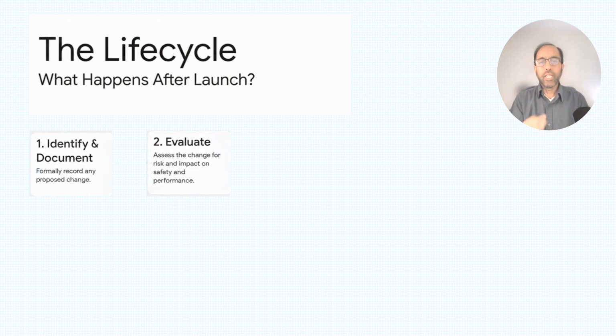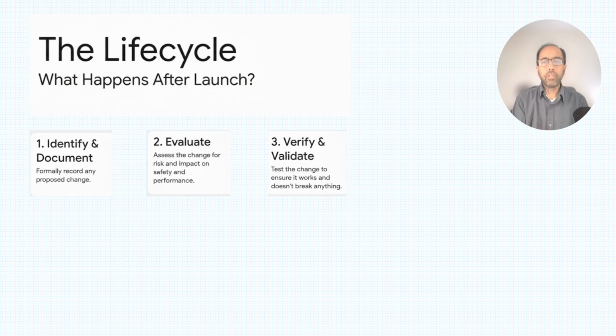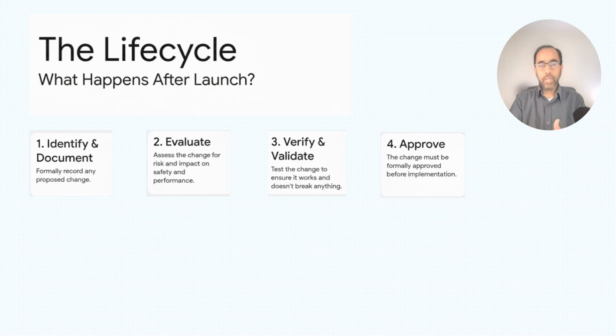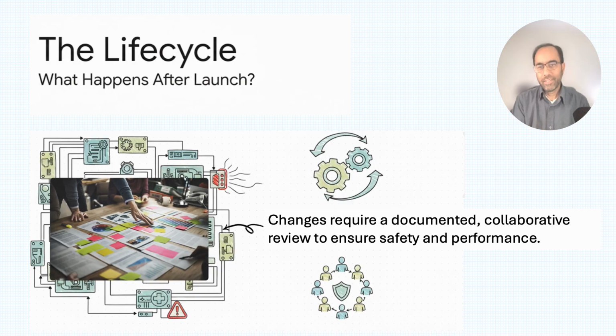Then you evaluate it by assessing the risk and impact on safety and efficacy. Next, you need to verify and validate the change to ensure it works properly and doesn't cause issues elsewhere. Only after that, the team can approve the design process, the change process. This isn't about bureaucracy, it's all about safety. It ensures that a seemingly harmless change to one part of the device doesn't have unintended, dangerous consequences for another part. That's the whole reason: safety and performance, safety and efficacy.